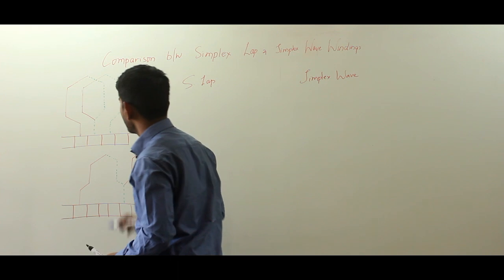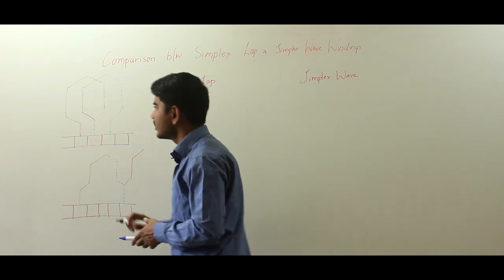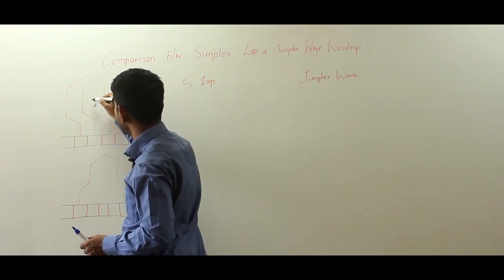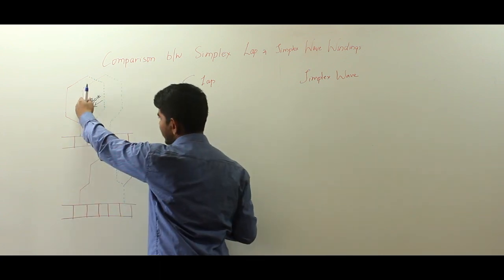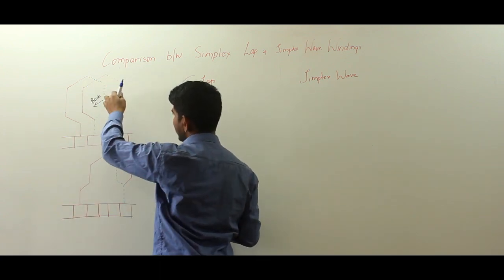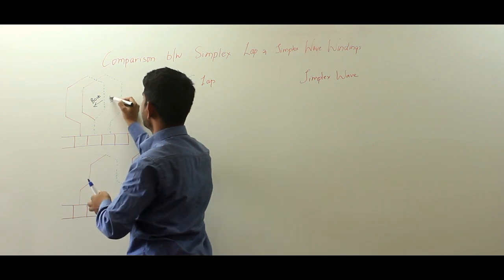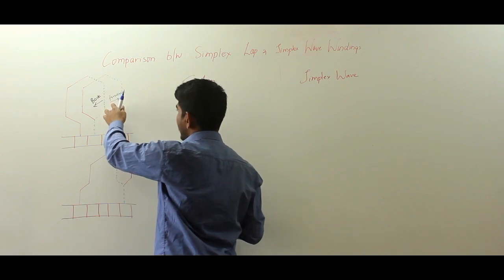These are the commutator segments. Here you can see the finishing side of the coil is connected to the starting side of the next coil, and this starting side of the coil is connected backward to the first coil. The starting side is connected backward and the finishing side is connected forward, so there is an alternate back and forward direction in this lap winding as the winding progresses forward.